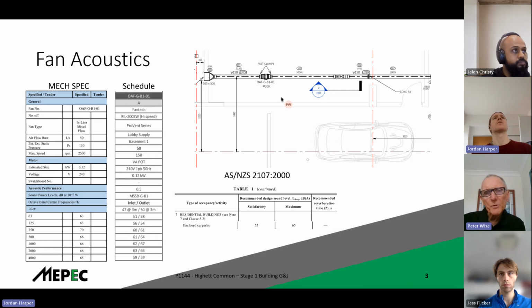Okay, a small fan in a car park like that's not going to cause any issues. No, the only issue might be if there's noise coming out of this louver and you've got a neighbour nearby, or the building itself - if there's say a residential apartment very close by, that may be an issue. But 47 dBA again, I don't think would be a problem. It's when you're getting up into the 60s, 70s, 80s that you're going to have issues.